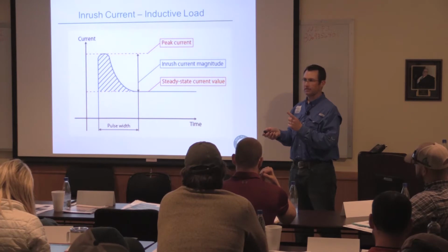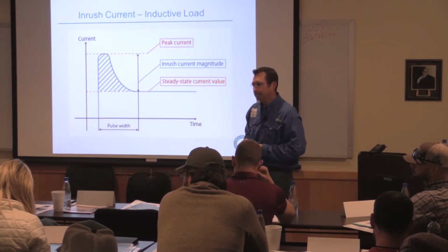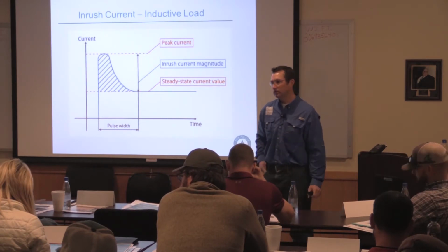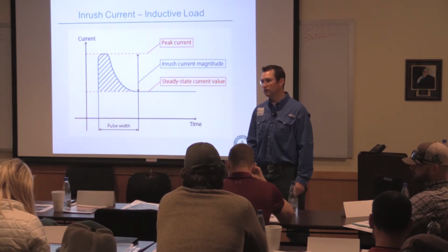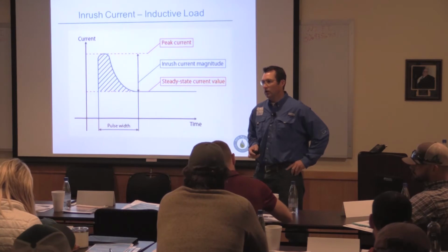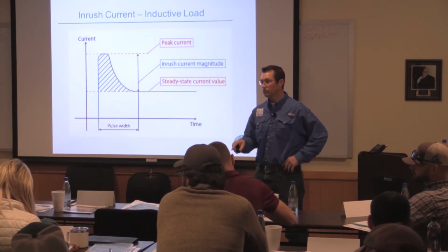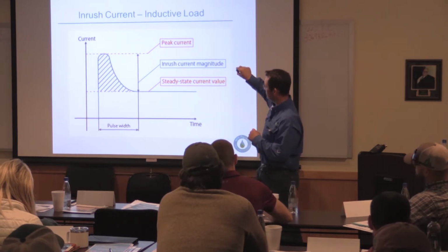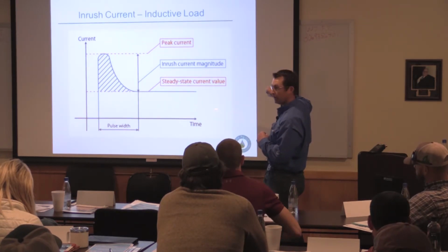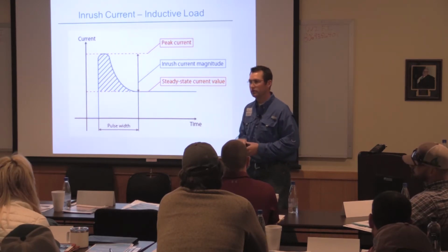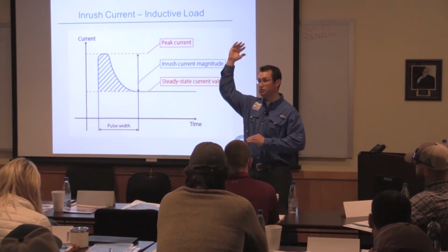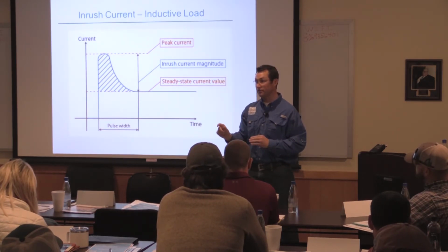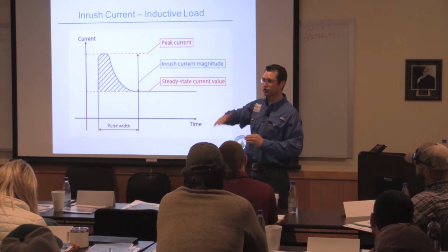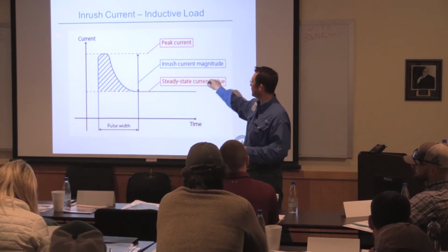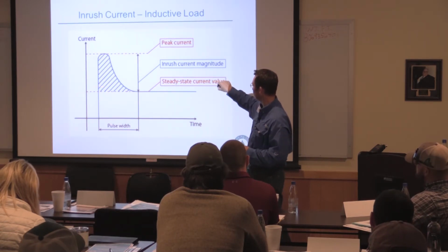I got a question on that, because I've asked that before and always assumed it was factored in, but they say no, that's done over a 15 or 20 minute peak use period rather than that initial starting period. Which story is correct? Well, I suspect it is, but if you look at this, here's where your start is, here's where your end is, and if you've got a start in the middle, that's contributing, but usually a very short interval. Yes, but the magnitude is huge. It may be just 2 to 3 seconds, but it's a huge number, so it contributes, but not like you're just paying base for this. Instead of paying for this, you're going to be paying for this.